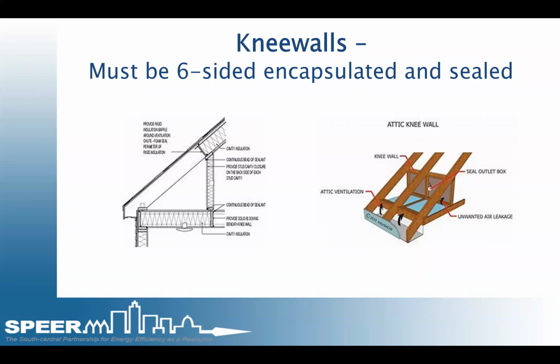But the load calculations and the sizing of the HVAC have been designed in consideration that these areas have been done properly with insulation and air sealing, and have obtained a Grade 1. Not having these details done correctly will lead to the HVAC unit not being able to meet the load and the occupants no longer being comfortable. This in turn leads to occupants turning down the AC, which increases the energy used to maintain comfort.